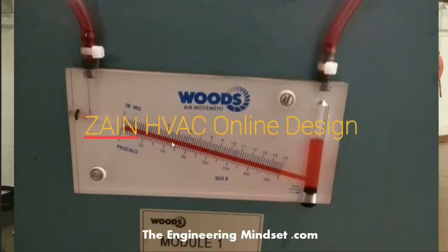This will change as the pressure increases across there. There's no pressure drop at the moment, but as the filter becomes more and more dirty, it becomes greater and greater. This is measuring the difference between the intake and the suction side across the filter, and that's how you know how dirty it is.